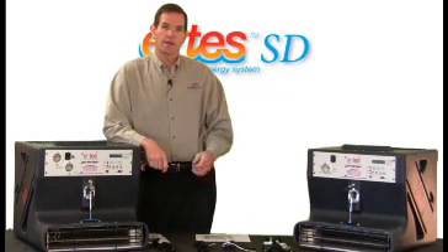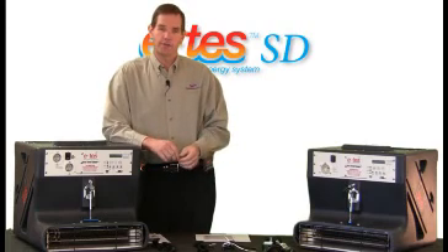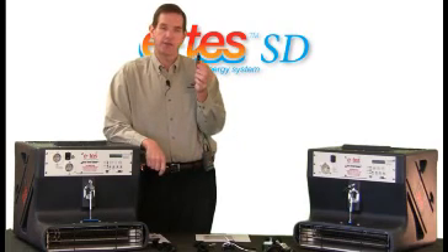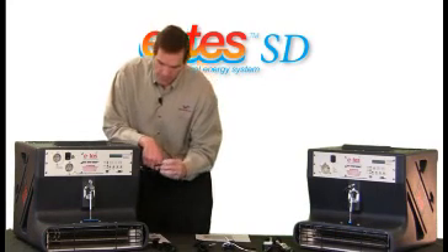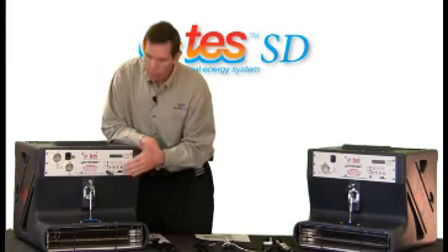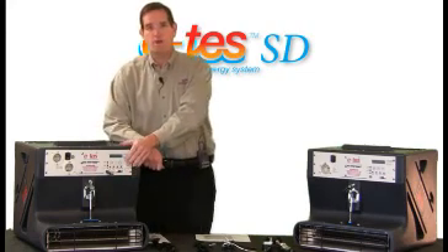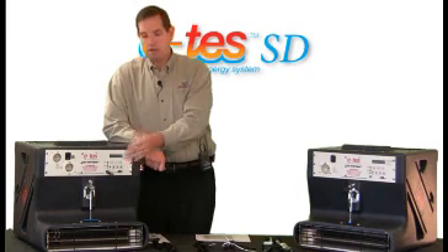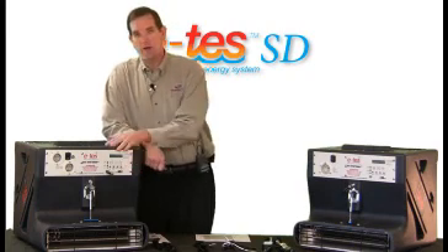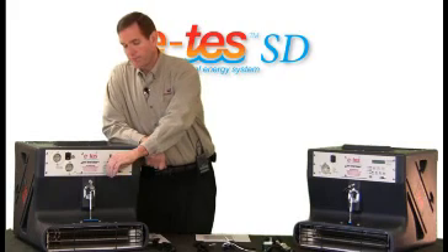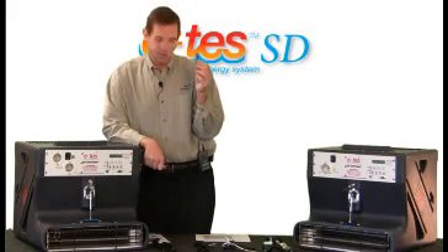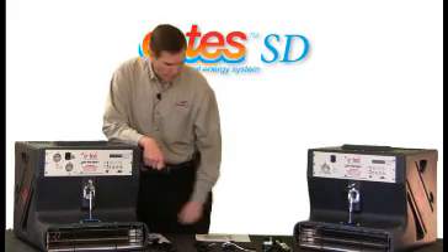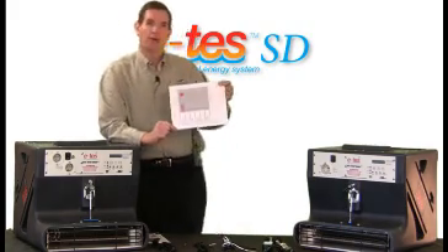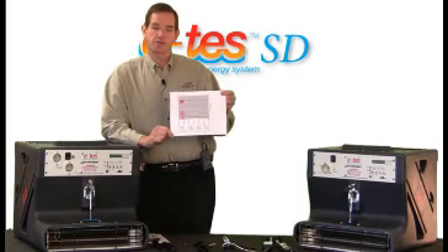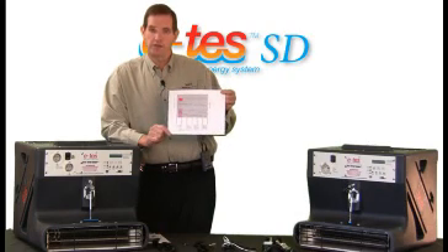To utilize the data logging and charting feature of the new E-Tes SD, you'll need to take a standard flash drive, thumb drive card, insert it into the port on the front of the microprocessing board control panel here, and then it will automatically download all the information from that job onto the flash drive. You'll then be able to disengage the flash drive, take it back to your office computer, laptop, whatever you choose to, and be able to print out documentation sheets. And so you can submit these with your invoicing to verify drying standards, drying times, etc.